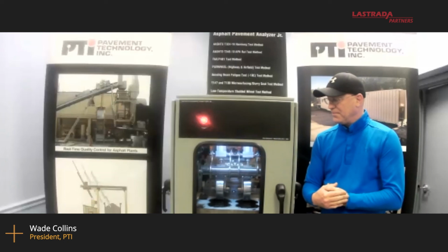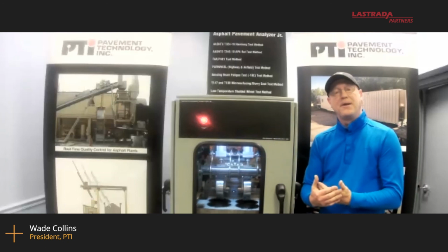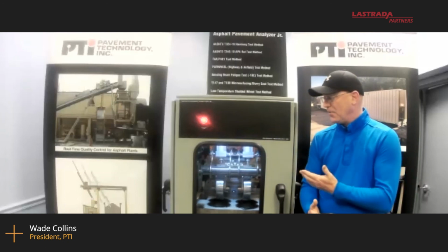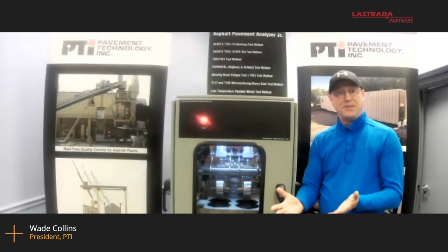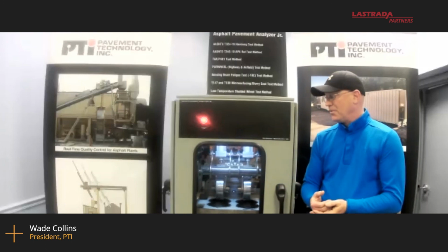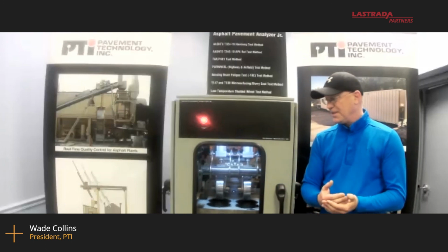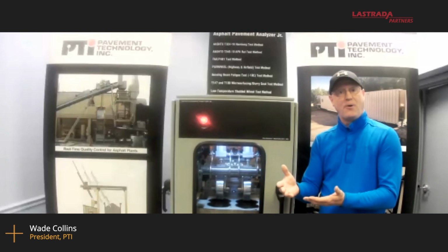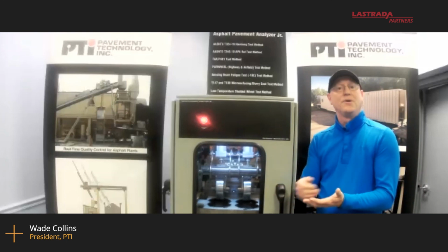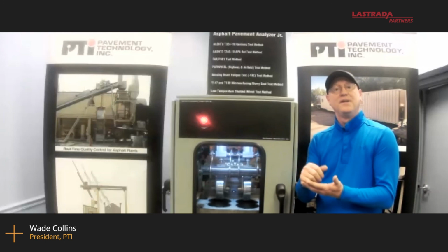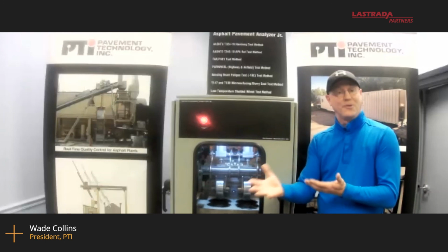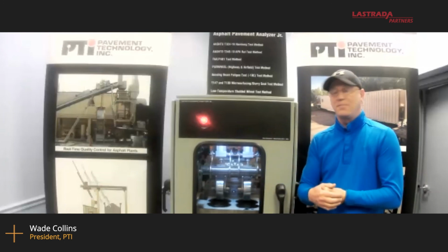Regarding maintenance, we have pillow block bearings on the linear rails here that we recommend they be greased periodically. We also recommend the water tank be cleaned periodically. It does have a spray bar installed inside of it. It's basically a self-cleaning system. You hook a water hose up to it, it will clean itself, and then the dirty water will drain out of another pipe.